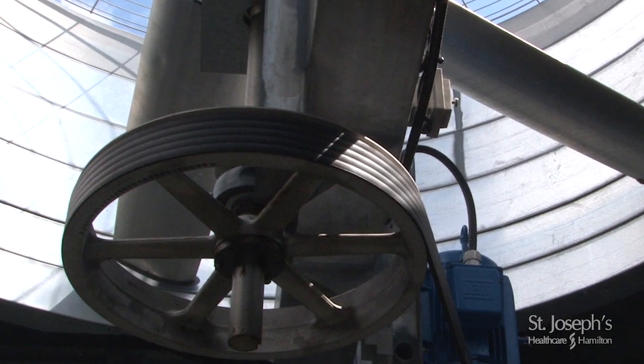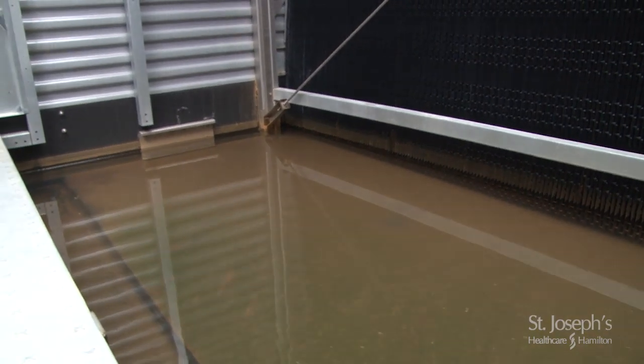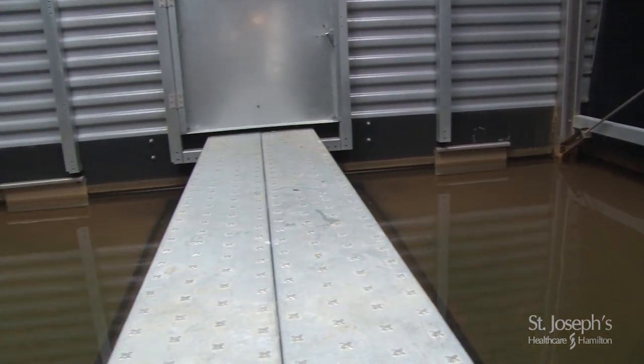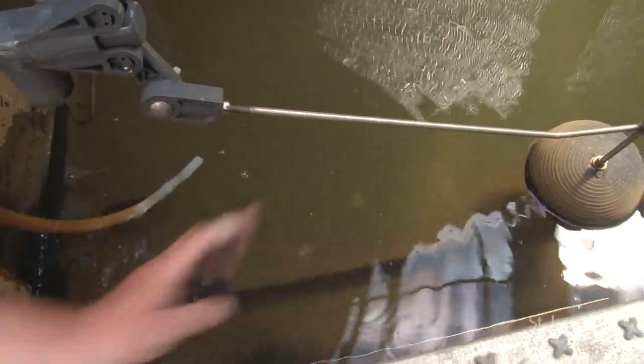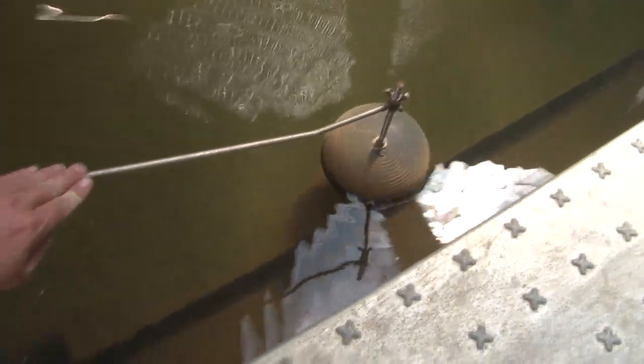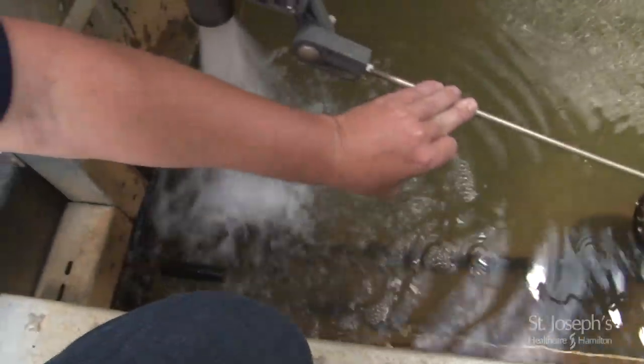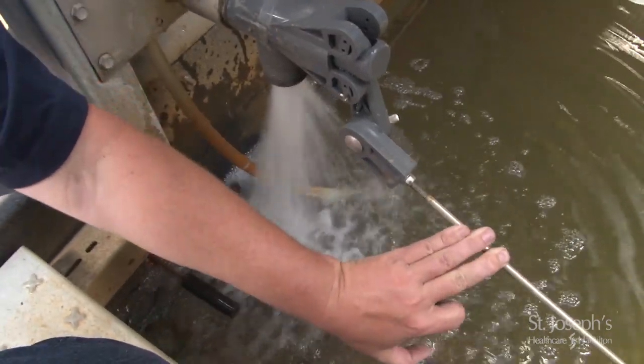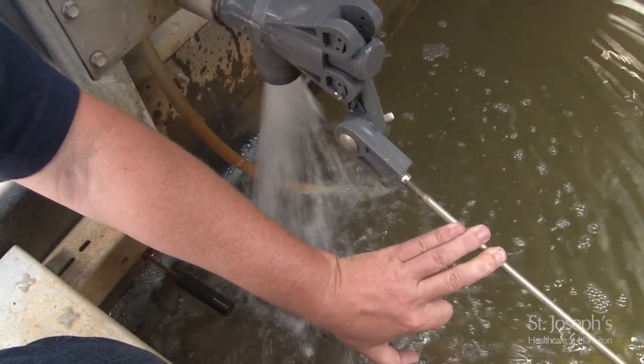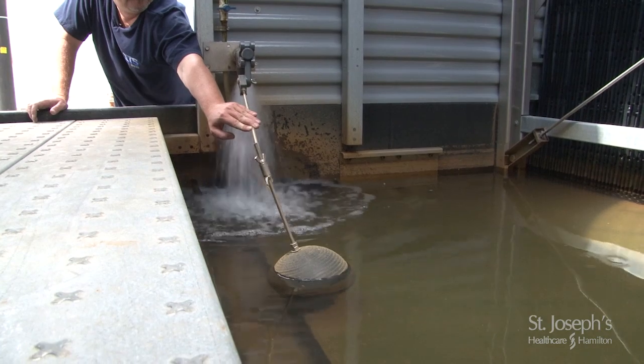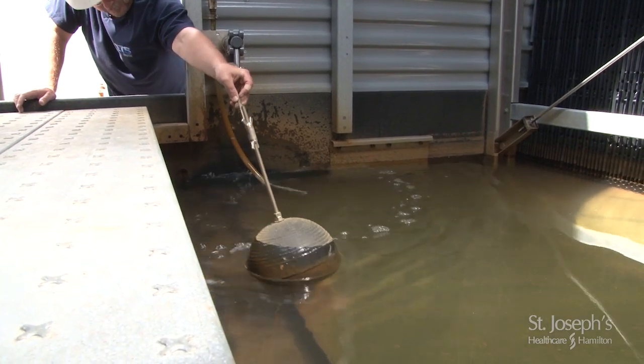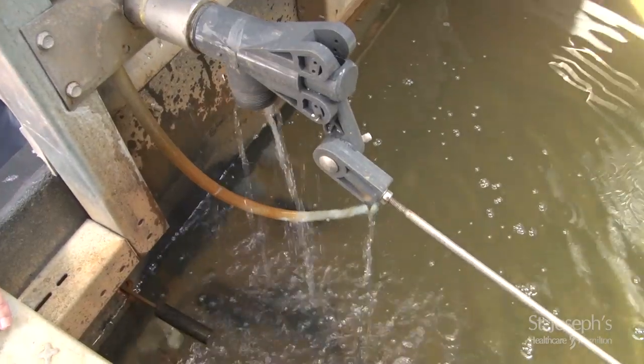The tower has a makeup assembly to keep fresh water within the basin of the tower. It's just a plunger system with a float ball on the end, and as the water level drops, the tower starts to make up water. As the tower level makes up and the plunger comes back up, the water stops filling.